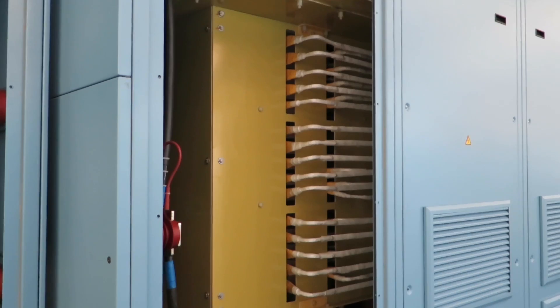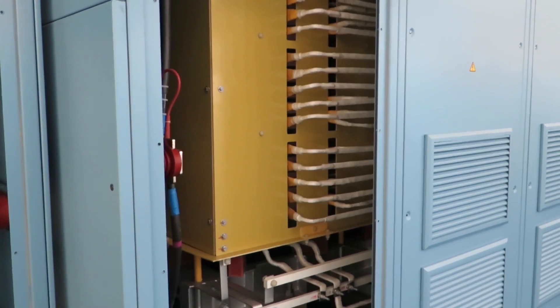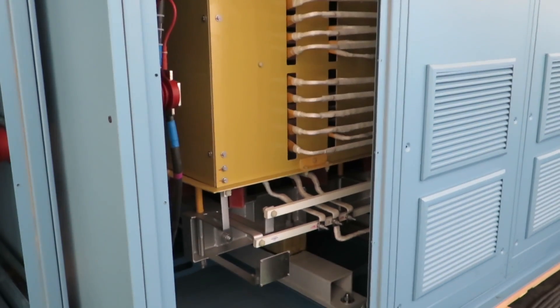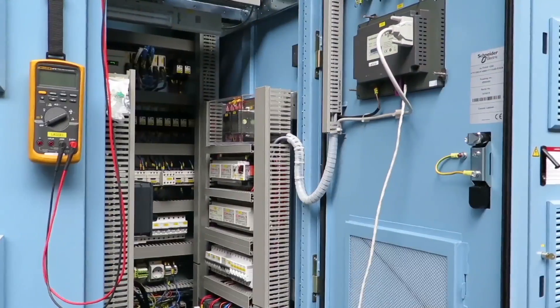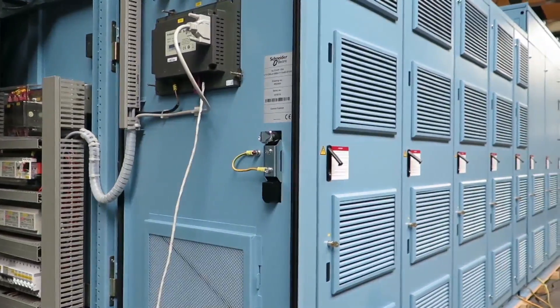This drive consists of two 7.5 MVA feeding transformers with 11 kV primary voltage and a multi-level configuration on the secondary side with 700 volt outputs.